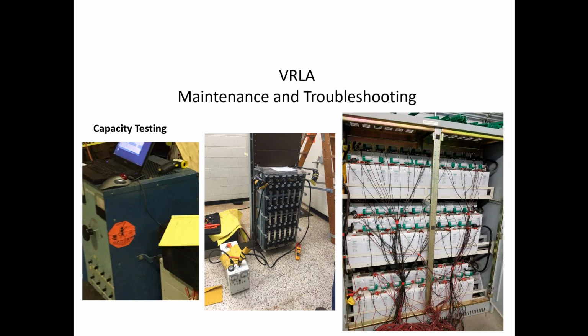Well, I was going to say, what loads do you use? Do they actually bring out a resistor bank, or do you just use, depending on the application, the actual load you're trying to test? No, we bring out a resistive load bank. We never want to jeopardize the equipment, because we are taking that battery to a terminal end voltage that may be very close to where the equipment cuts out, depending on what you're supporting.